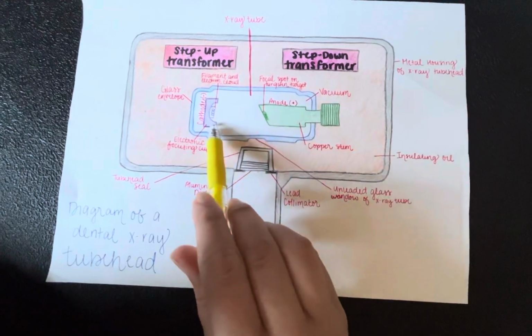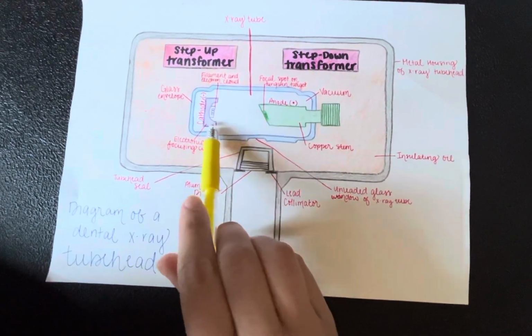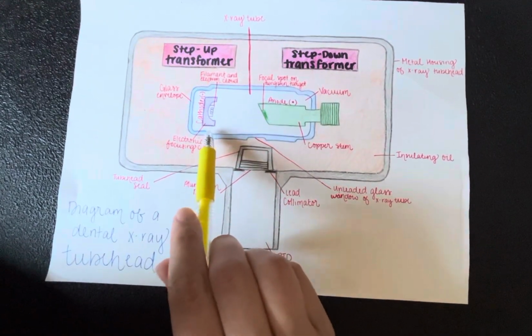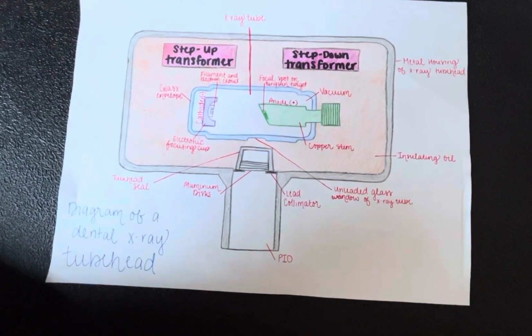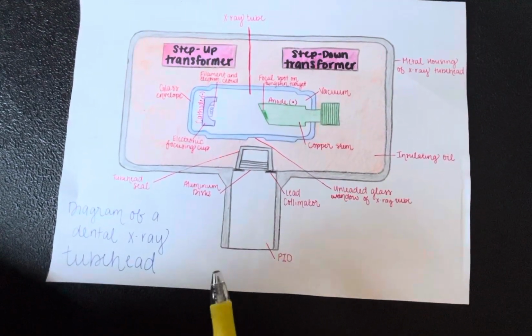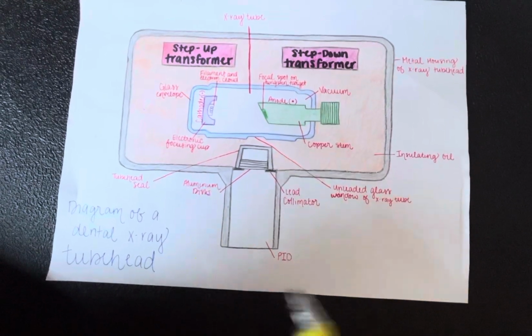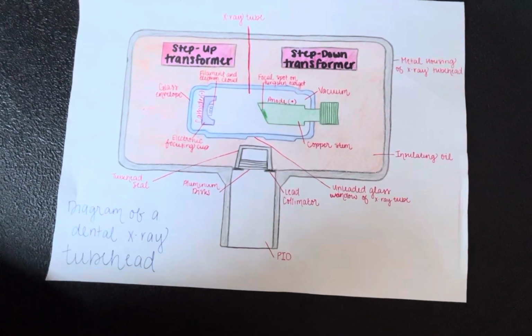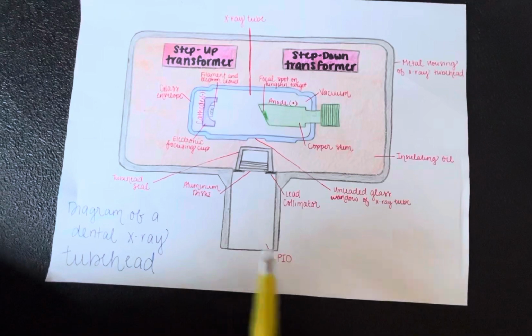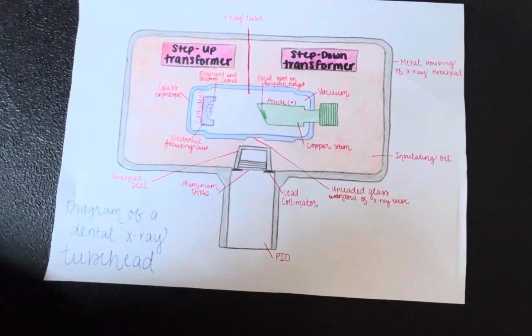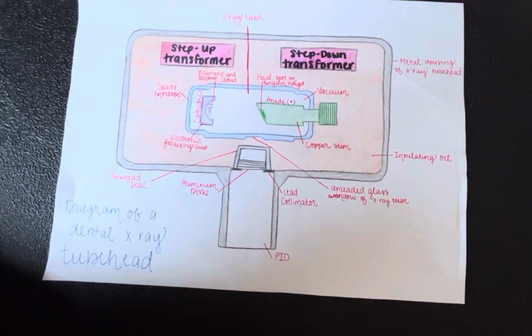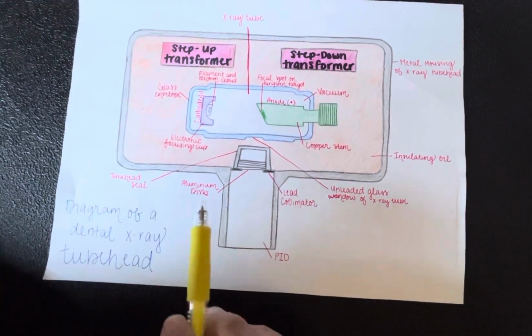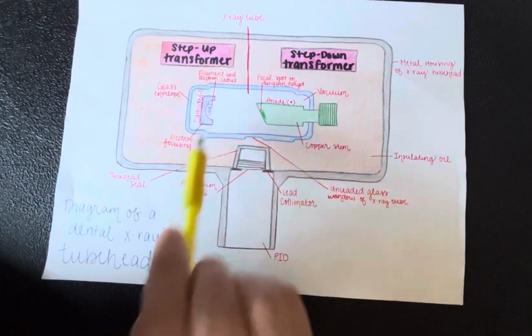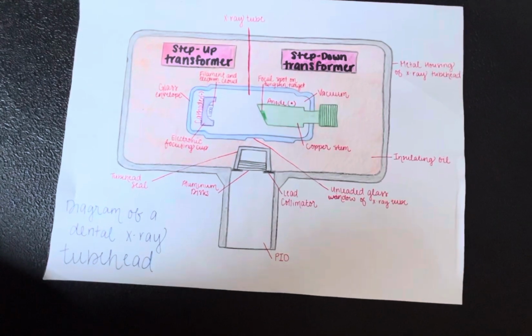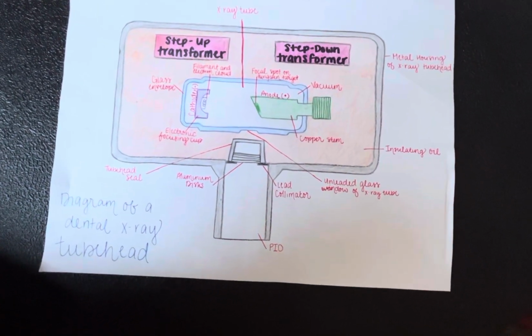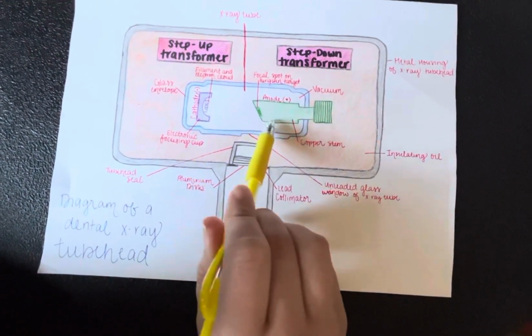The cathode, or negative electrode, consists of a tungsten wire filament in a cup-shaped holder made of molybdenum. The purpose of the cathode is to supply the electrons needed for X-rays. The tungsten filament is a coiled wire made of tungsten which produces electrons when heated. The molybdenum cup, or electron focusing cup, right here, focuses the electrons into a narrow beam and directs them across the tube towards the anode.